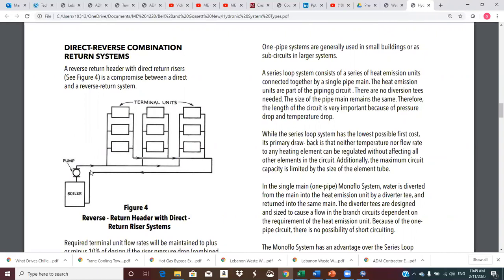The furthest riser, we come all the way down here, up through the coils, down, and then a relatively short return. And this one's intermediate. So that's reverse return on the header, but the risers are direct return. So we go up short path, down; long path up, long path down. So, you know, there are guidelines, and there are all kinds of possibilities in doing this sort of thing.